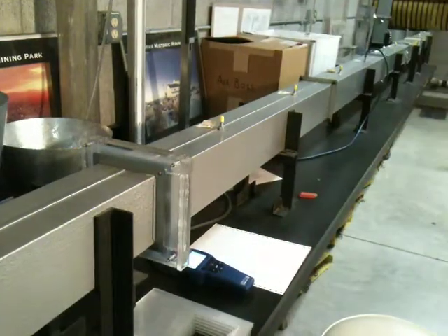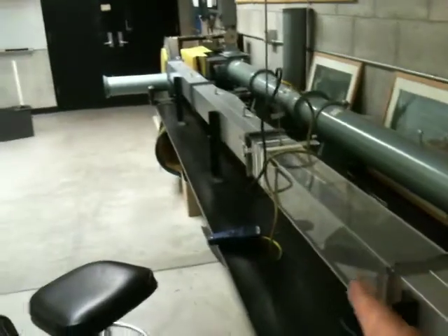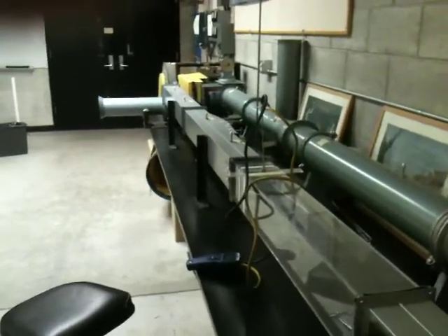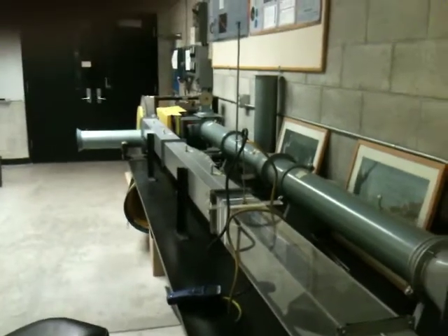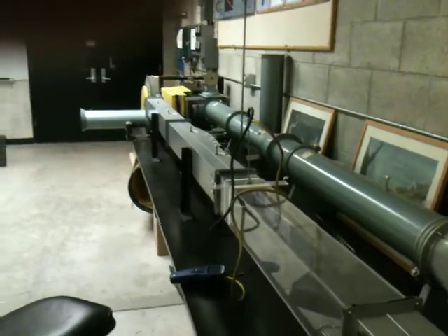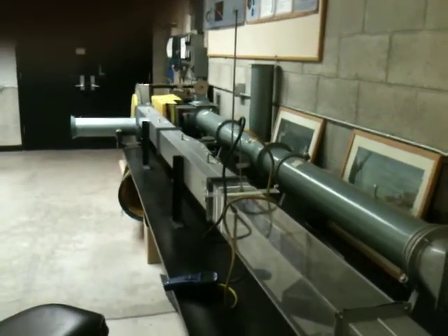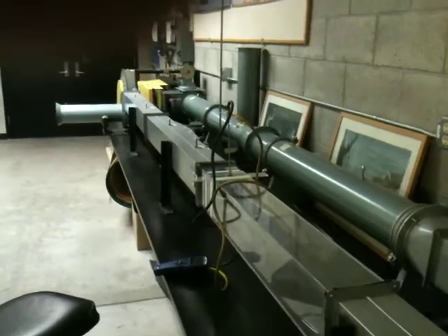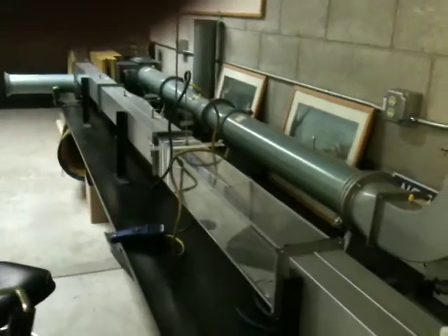Let me show you the setup here. For this exercise and all the rest of them, we're going to have two manometers set up. We have one manometer set up at the pitot tube traverse section that we did previously, and we're just going to be recording centerline velocity pressures there. You'll calculate the centerline velocity, and then you'll multiply that by the correction factor to get the average velocity in the airway. And then you'll multiply that in most exercises by the cross-sectional area to get Q.